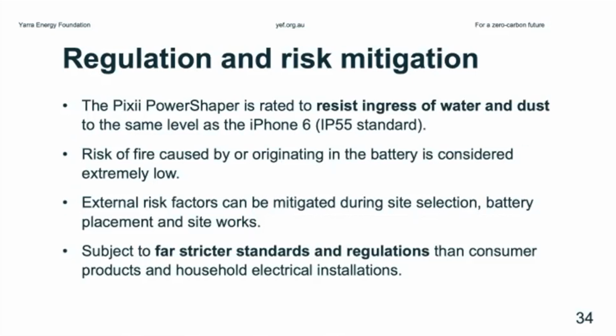That reduces risk in various ways, risk of inundation, things like that. The risk of fire caused by or originating in the battery is considered extremely low. I'll go into why on the next slide, but more likely, if there were to be a fire associated with the battery, it would be derived from an external source. So that's a bigger consideration for us when it comes to site selection, battery placement, and site works. We're more focused on external risk factors, because the risk of the battery itself catching fire on its own is extremely low.